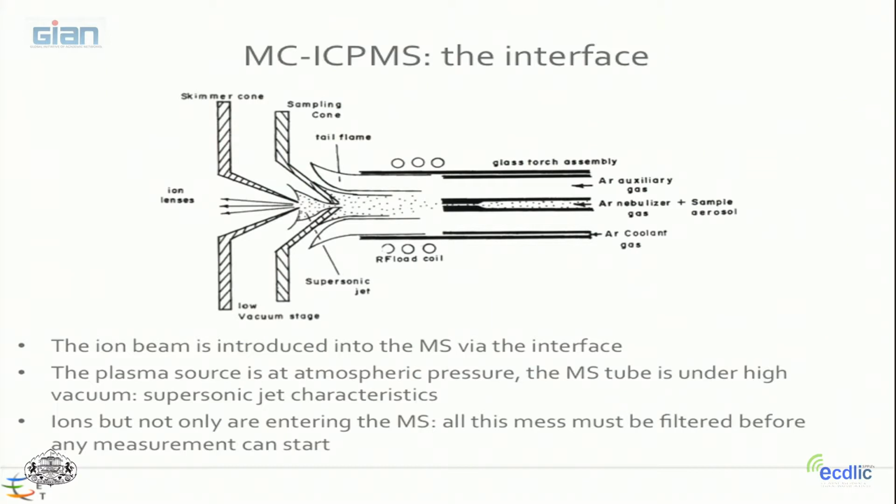You are throwing your ion beam at a supersonic speed, so that here you have a zone which is under vacuum. And you create an intermediate vacuum, and the way you do it, you have 2 cones with different geometry. We call it the interface, and in fact, the ion beam is collected within this interface. And thanks to this, you can switch from 1 atmosphere to 10 to the minus 9 because of the supersonic property of the ion beam. Okay?